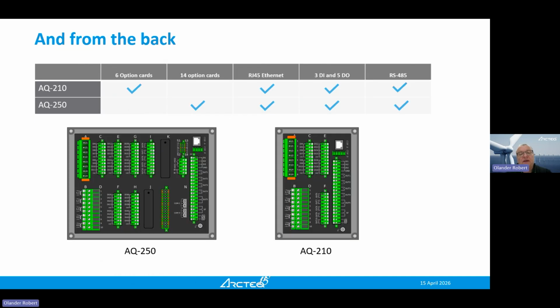If we take a look at the back, you can see on the right-hand side of the device the motherboard. So there we have the processors. There you have another Ethernet connector, mainly for protocol communication. There is an RS485 connector for RS protocol communication, and then as standard we have 3 digital inputs, 5 digital outputs, and then the power supply on the right-hand side. Everything else is done with option cards. So if you need more analog inputs on current or voltage, if you need more digital inputs or outputs, you just add cards. If you need RTD inputs, if you need milliampere inputs, you add that. And then we also have cards for different types of communication.